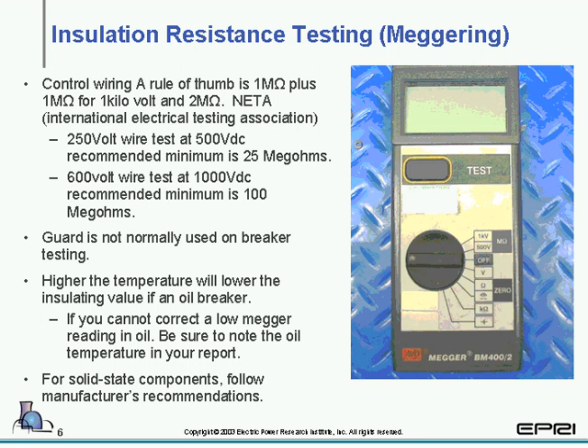We have one more slide, and we'll be taking a look at the control wiring. Now, one of the rules of thumb is 1 megaohm plus 1 megaohm per kilovolt, and it should be at least 2 megaohms. So in other words, if you have a 5 kV piece of equipment you're measuring, you would expect to see 5 megaohms plus 1, or 6 megaohms.